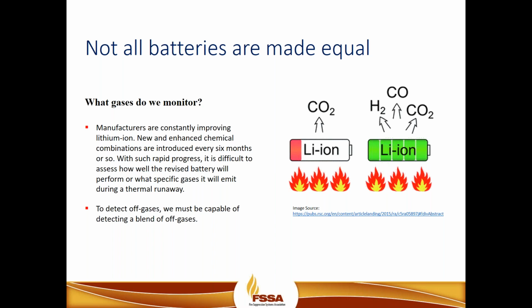Also, fixed type sensors are challenged by the environment. Many times the energy storage systems are built in high airflow environments where you're looking at cooling the racks or modules themselves. So much like when we consider smoke detection in mission critical type facilities, you have the requirement to detect smoke as it moves through the path of airflow. And traditional fixed type sensors are challenged to detect in these types of environments. So being able to detect in high airflow environments, and also the lack of cumulative detection that we see from fixed type sensors, creates a challenge for the traditional technology. So no matter the situation, in order to prevent thermal runaway, we need a complementary solution with a battery management system and an active early warning detection system.